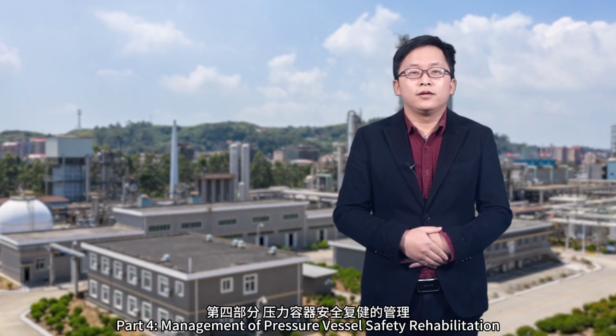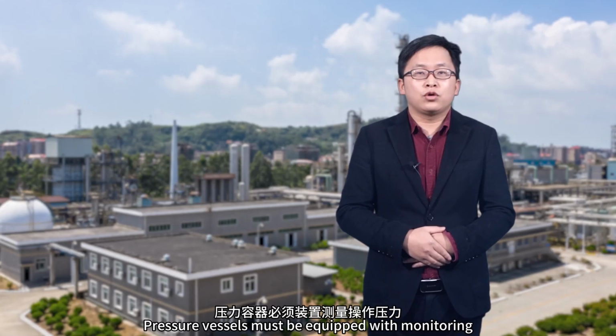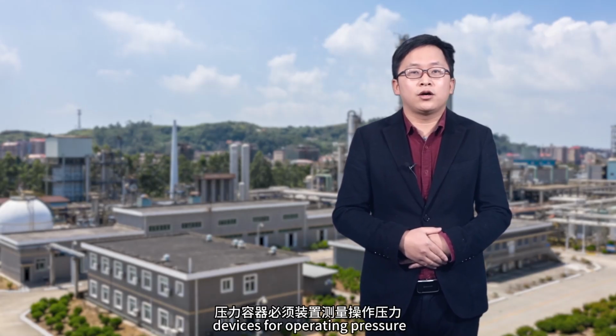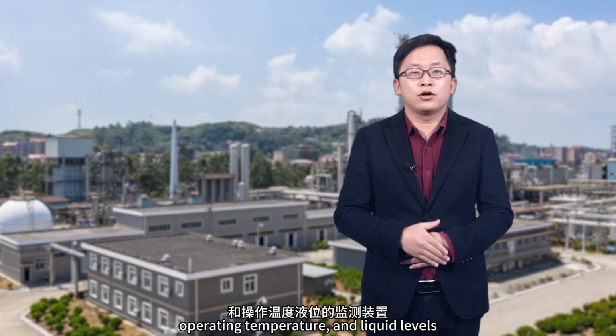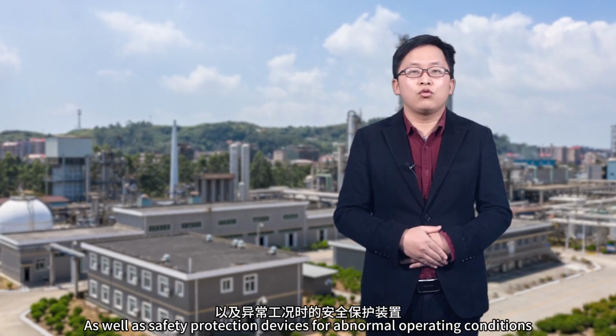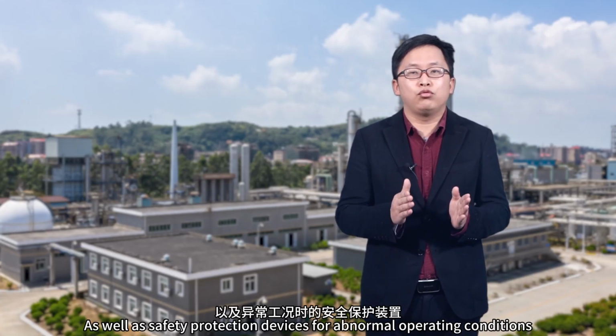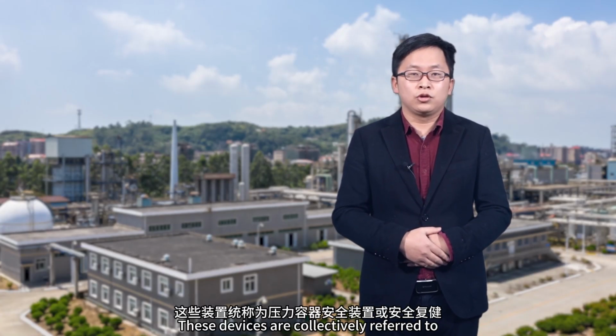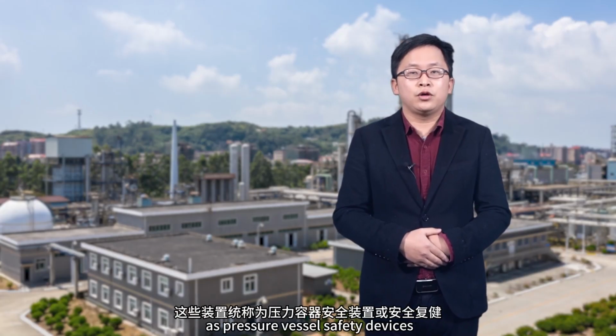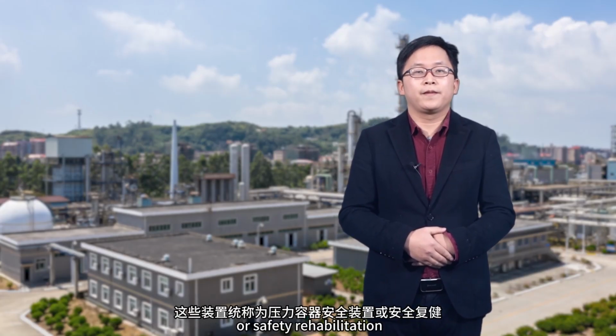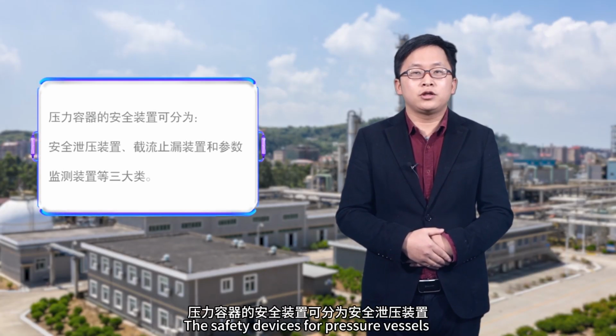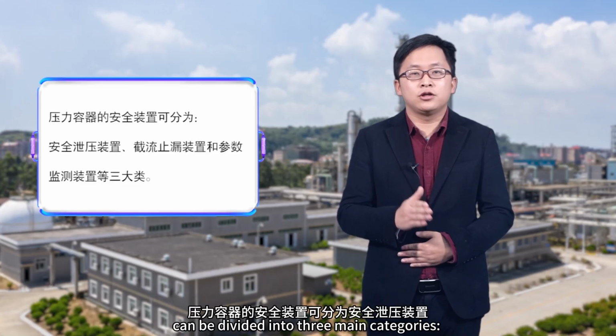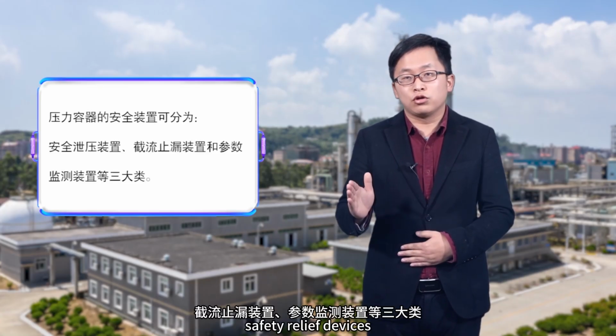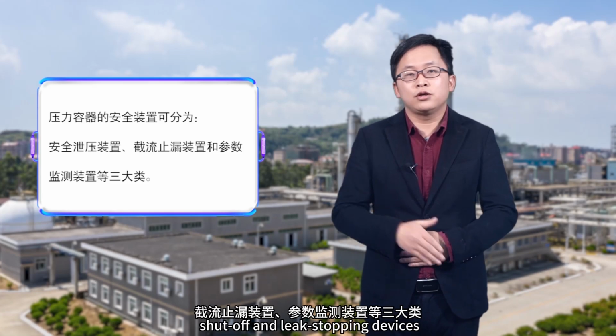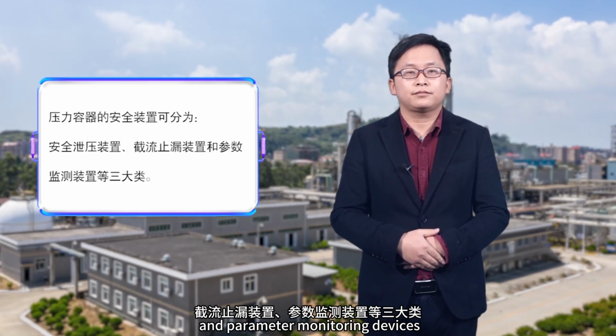Part 4. Management of pressure vessel safety rehabilitation. Pressure vessels must be equipped with monitoring devices for operating pressure, operating temperature, and liquid levels, as well as safety protection devices for abnormal operating conditions. These devices are collectively referred to as pressure vessel safety devices or safety rehabilitation. The safety devices for pressure vessels can be divided into three main categories: safety relief devices, shut-off and leak stopping devices, and parameter monitoring devices.